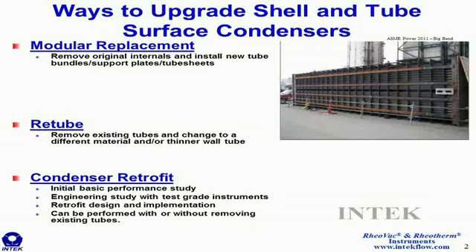The better performance could result from cooling water flow increase due to lower hydraulic pressure drop across the new module, or more condenser surface area, or better heat transfer material. As you might expect, a modular replacement can be a very costly project in terms of labor, logistics of moving large components. And in fact, a modular replacement may not even be an option because you can't maneuver a module into the building. So another way to upgrade the condenser is a condenser retube. This is when the old tubes are removed, a new, better heat transfer tube can be selected and installed, and a very small % heat transfer increase can be expected with this option.